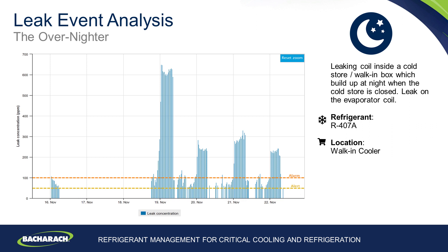You can clearly see the leak rise and fall. If an engineer attended site during the day with a handheld leak detector, they may not detect the leak and question the efficacy of the detector. When we visualise the leak, you can clearly see the dynamics of it — the cause, the effect, and when you should be trying to find it. This type of leak is going to be difficult to find and very small, but with some perseverance and visualisation it will be found and rectified. It may not even contribute to any refrigerant loss or system performance issues, thus mitigating costs.